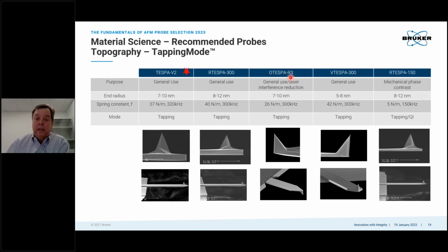And then there's the O-TESPA and the V-TESPA. This is a very different shape to the probe. They're still silicon tapping probes, with very similar resonant frequency and everything, but the tip itself is right at the end of the cantilever. If you look from the back at the optics, the very end of the cantilever is where the tip is. So if I have an application where I'm trying to land on a very narrow area, like a particle or a very specific part of the sample, these are nice probes because the end of the cantilever really is where the tip is. So it has a slightly different shape, versus these probes, which are slightly recessed, although still very good probes, and I tend to use these more.